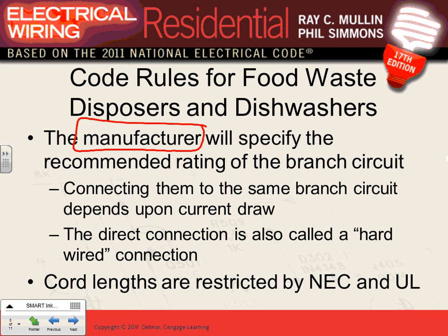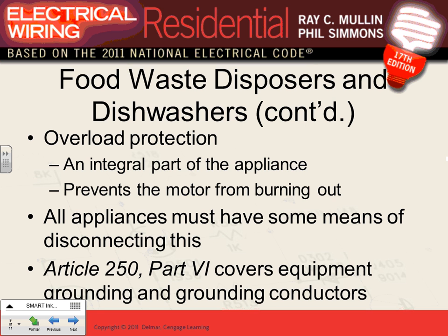You can have a direct connection, as I said, also called hardwire, but be aware that you have to provide some type of disconnect for your equipment. So that's in terms of overload. We talk about all this equipment having to have an integral overload protection, guys, to protect it from being overloaded and burning the equipment.